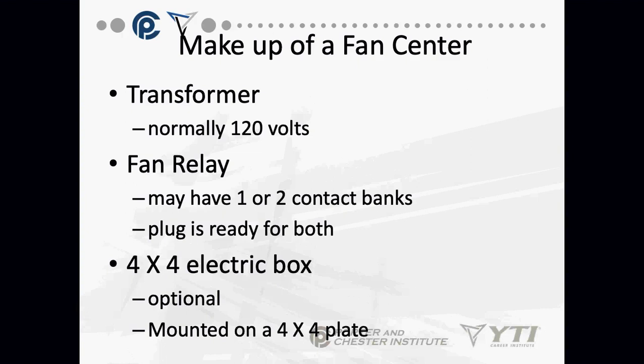A fan center has two parts in it. We've already talked about these two parts. That's why I'm really not all that worried about it. You have a transformer, which is 120 volt to 24 volt, and you have a fan relay. It's a Mars relay mounted in the box, and it all comes pre-wired. So you have nice little connections where you can put your R wire, your C wire, your Y, your W, and your G. Okay, so the fan center is a Mars relay and a transformer.